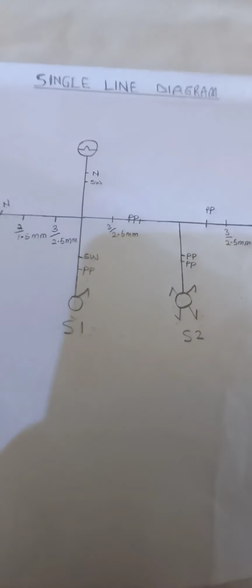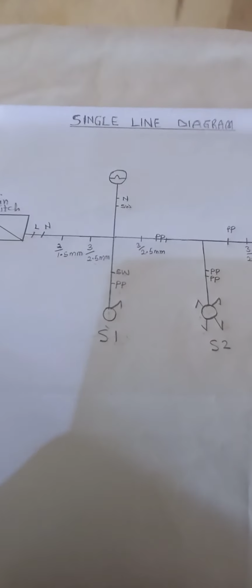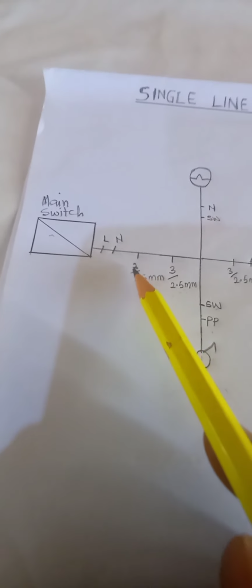If not, you may be given a wiring to wire but not know how to draw, or you may be given the drawing but not understand it, so your work will not be carried out properly. So whenever you see this, it means there are 3 wires in the pipe that are 1.5 mm. As you all know, 1.5 is for lighting, and this shows that there are 3 wires in the pipe that are 2.5 mm. That one is for sockets. And here is the symbol for sockets, and these are the symbols for switches, lamp, and then the main switch.